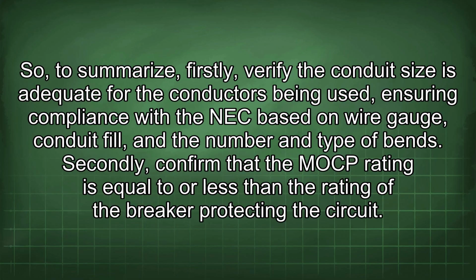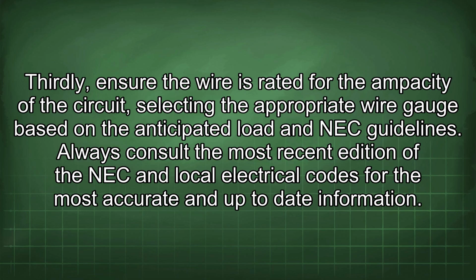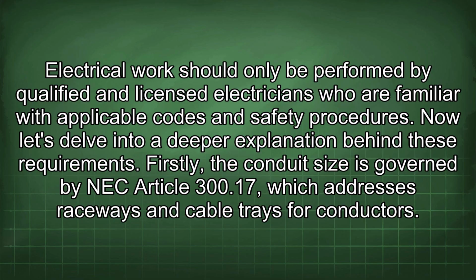Secondly, confirm that the MOCP rating is equal to or less than the rating of the breaker protecting the circuit. Thirdly, ensure the wire is rated for the ampacity of the circuit, selecting the appropriate wire gauge based on the anticipated load and NEC guidelines. Always consult the most recent edition of the NEC and local electrical codes for the most accurate and up-to-date information. Electrical work should only be performed by qualified and licensed electricians who are familiar with applicable codes and safety procedures.